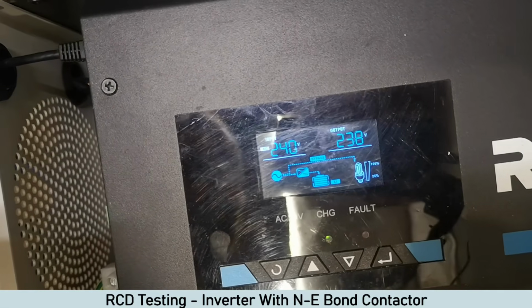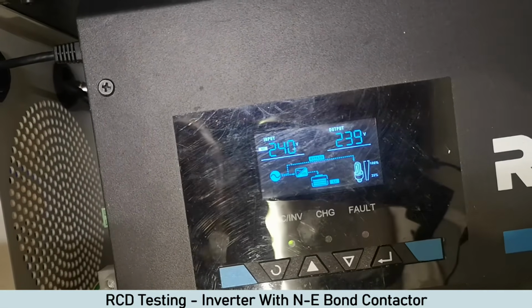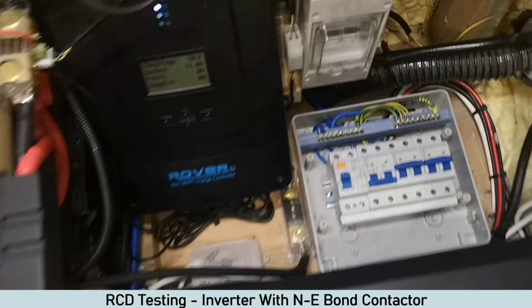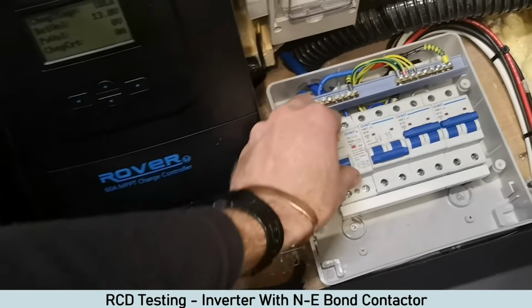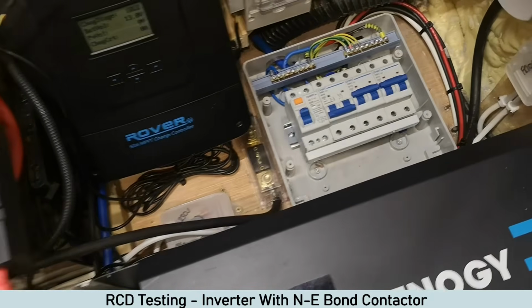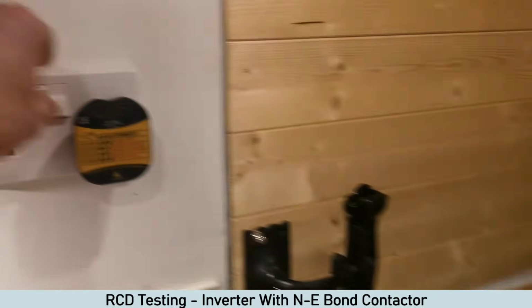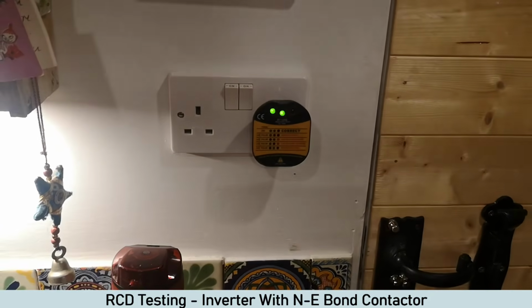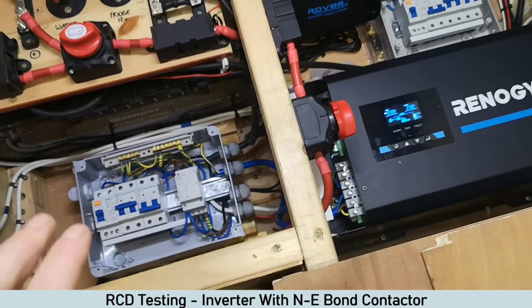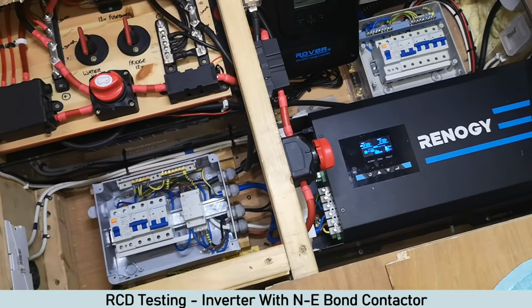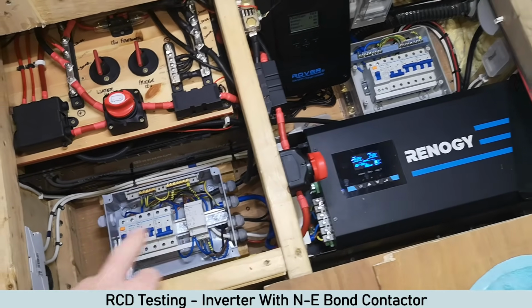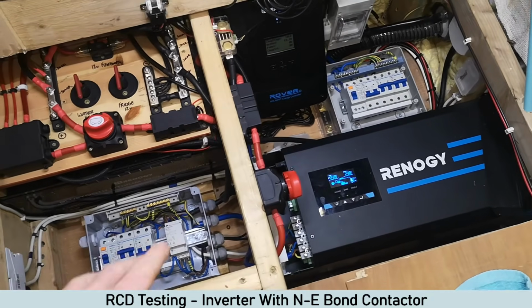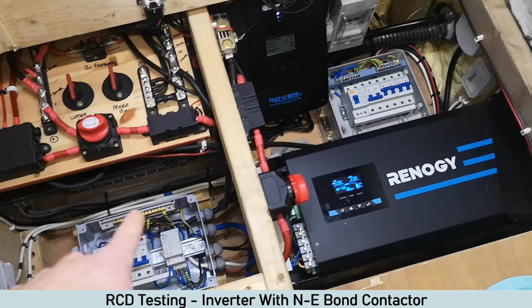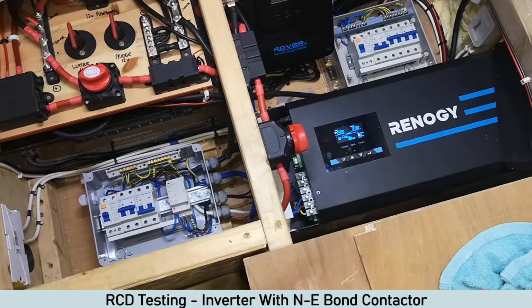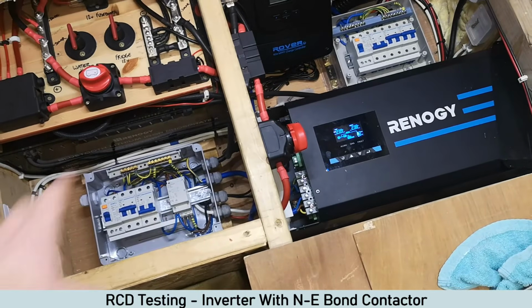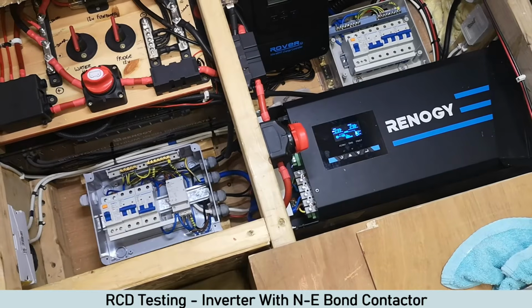Here we go. So now the inverter charger's in bypass. So the way we had it before, obviously the RCD will trip out. That's going to work. And then I'll go up to here again. Correct, happy days. Just to do a bit more of a demonstration, what I'm going to do now is turn the socket tester on. Currently we're on hookup, so that's in bypass. So I'm going to plug the tester in, switch the hookup off, and we'll see what happens to the tester, and then I'll switch the hookup back on and see what happens there.